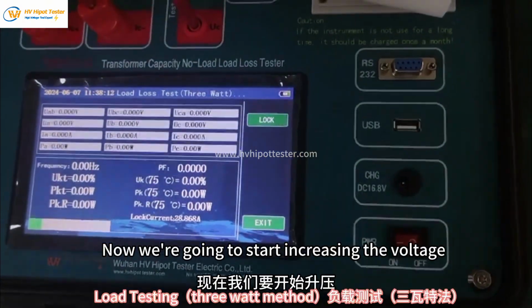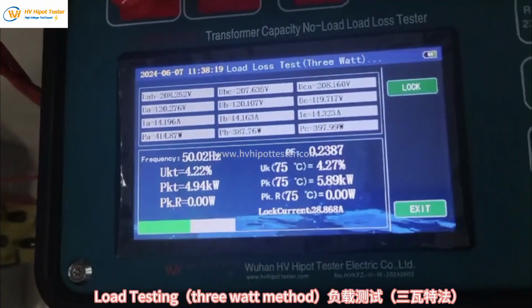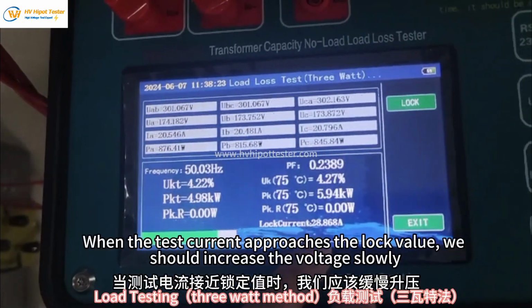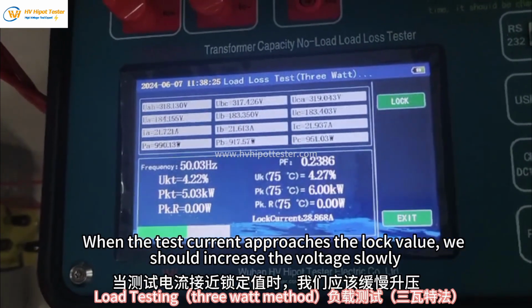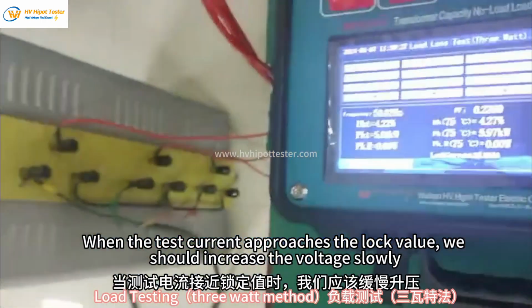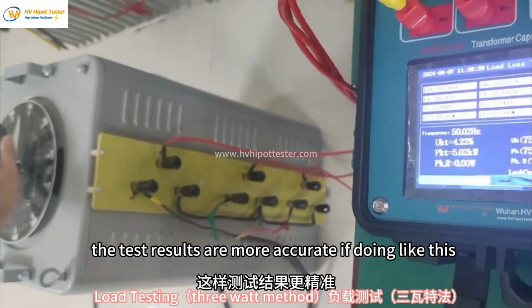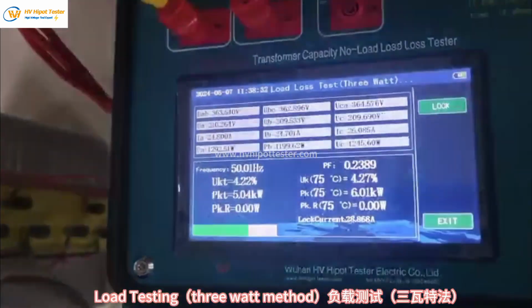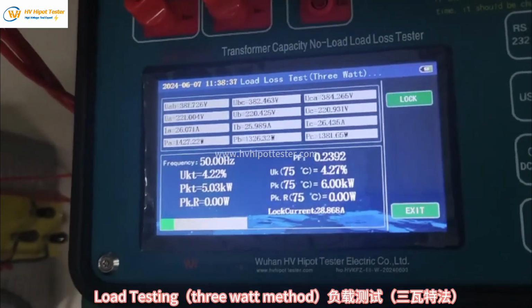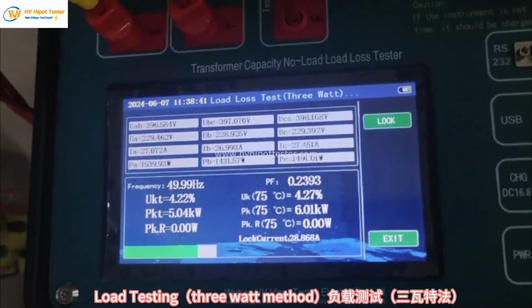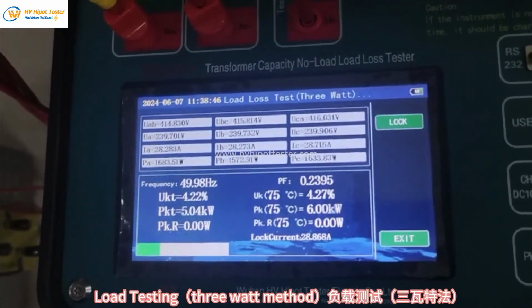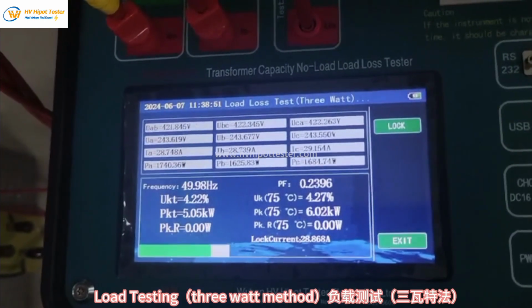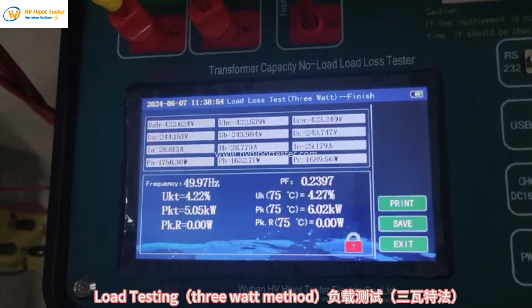Now we are going to start increasing the voltage. When the test current approaches the lock value, we should increase the voltage slowly. The test results are more accurate if doing like this. Now the test is locked.